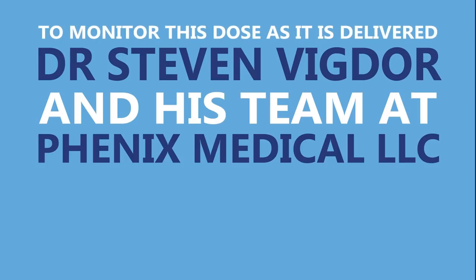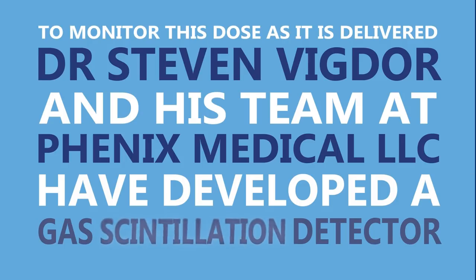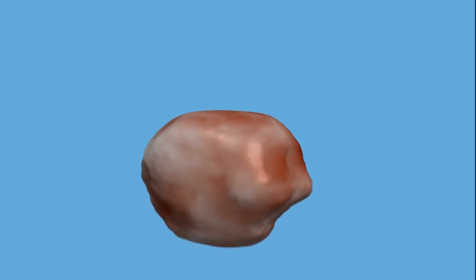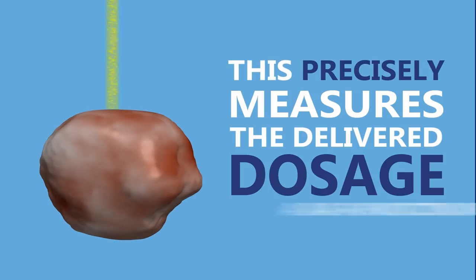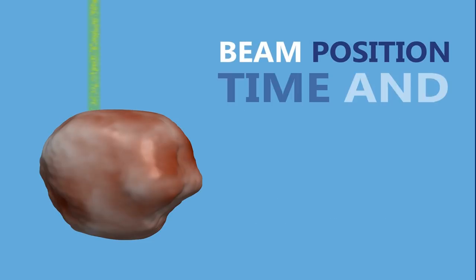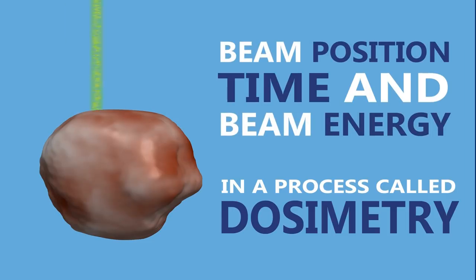To monitor this dose as it's delivered, Dr. Stephen Vigdor and his team at Phenix Medical LLC have developed a gas scintillation detector. This precisely measures the delivered dosage as a function of beam position, time and beam energy in a process called dosimetry.